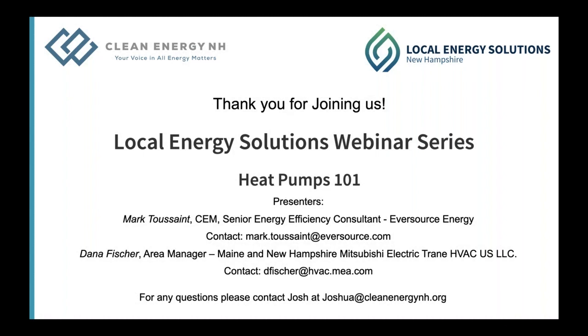But really, you're deciding what you're going to heat your home with for a very long time. Boilers last for like 15 years, or 20, or longer. So when you choose to replace an oil boiler and put in a new oil boiler, you're choosing to do that for decades. And if you look at the cost savings over that period of time, and you think about it from the perspective of financing or a home equity line or something along those lines, it's not too difficult to really justify switching over to heat pumps.